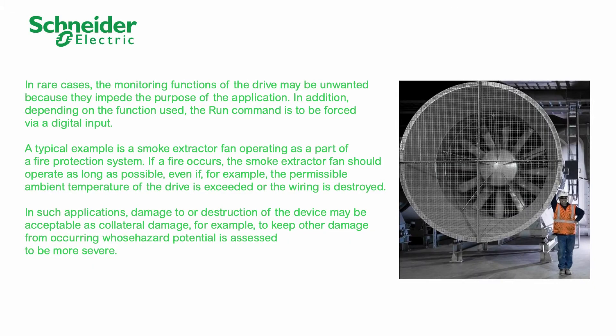In rare cases, the monitoring functions of the drive may be unwanted because they impede the purpose of the application. In addition, depending on the function used, the RUN command is to be forced via a digital input. A typical example is a smoke extractor fan operating as part of a fire protection system.